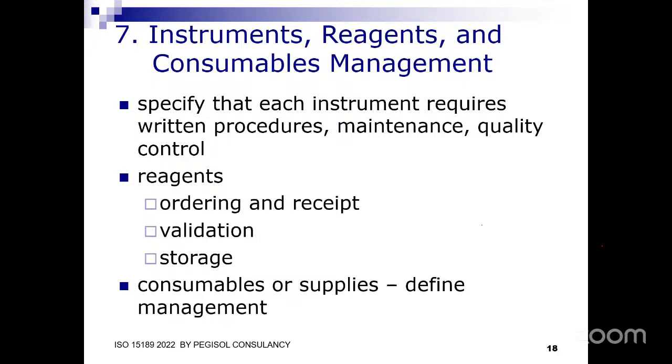Let's say, for example, you can say every equipment, every test has to be validated before such test is being put into use. Now, our validation protocol for analytical, let's say quantitative testing, is a minimum of 30 samples within run and between run.